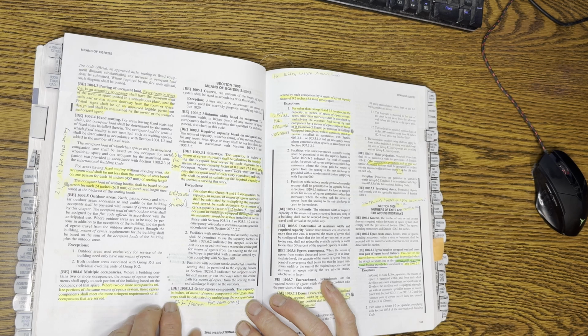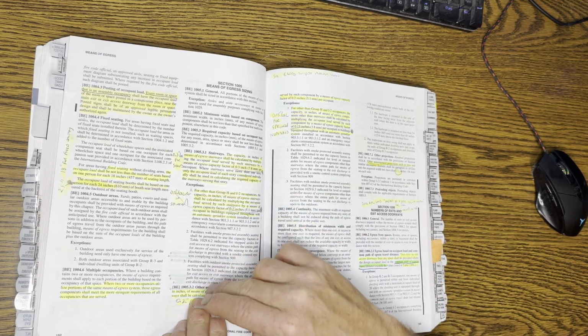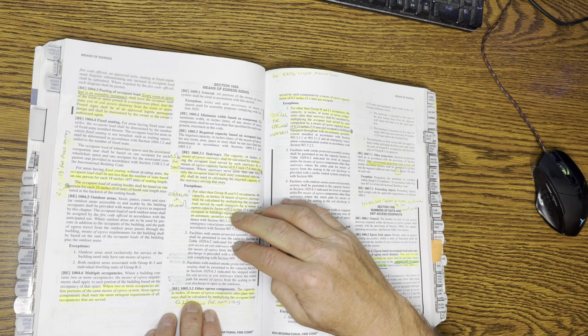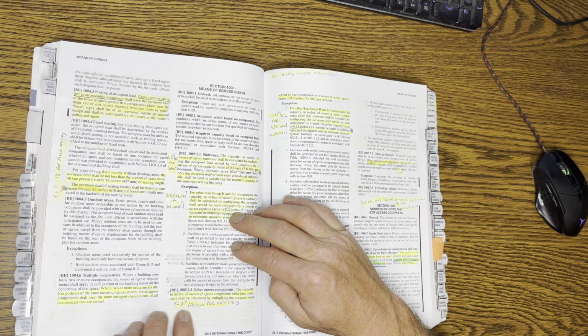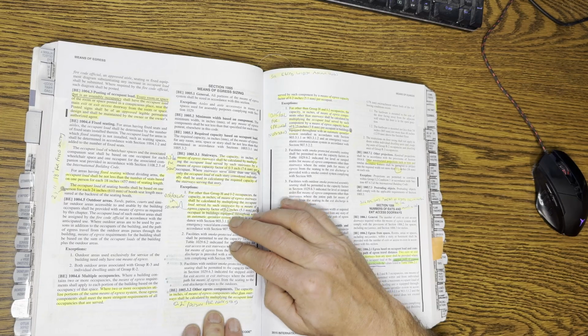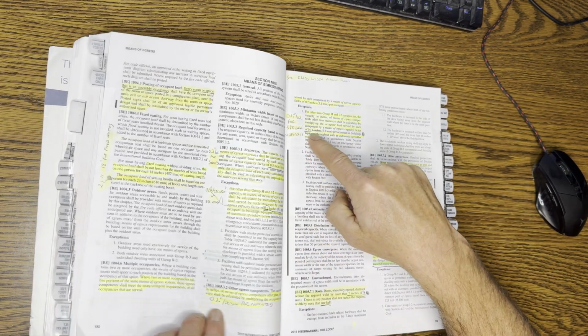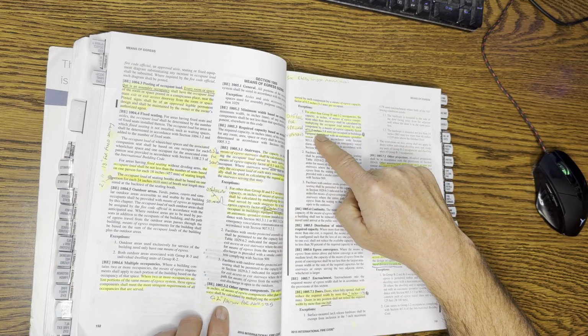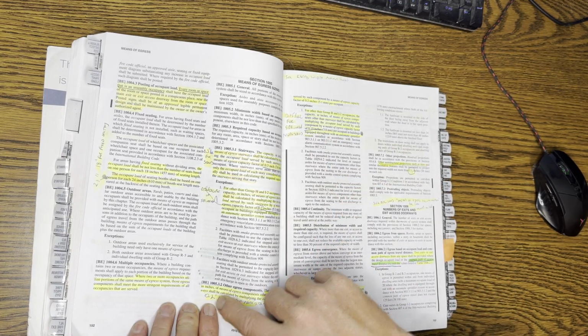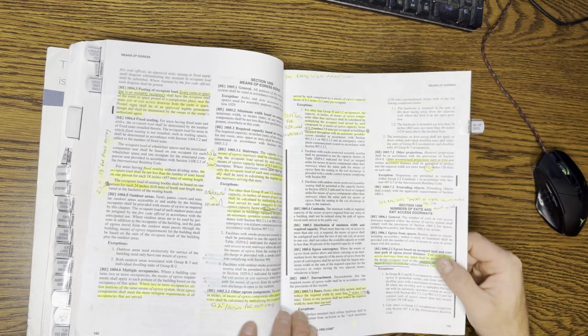Okay, so down here, the capacity for other means of egress. What do I mean by that? I mean corridors and doors. Okay, doors. So it's actually 0.2 for non-stairs, non-suppressed. Up here, it's 0.15, so it's right there. Once again, this is not available in NFPA 101. It's 0.2, not 0.15. IFC gives you a little bit more latitude.